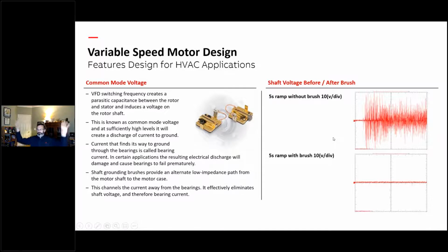And it's kind of like the electrical globe science theater thing. If you have a big enough voltage potential between two conductors, you'll get an electrical arc that'll actually discharge across. So it's like the old sci-fi movies where you see those little bulbs and electrical arcs. It's really no different. You ionize the air between the two conductors, and you have a little mini lightning bolt. And that little mini lightning bolt literally anneals the bearing races, makes them brittle, and then they pit out and cause your bearing to fail. So this is before a shaft grounding brush, and this is after. It basically takes all this and shunts it to ground and removes it from the system. And that's why they're recommended.